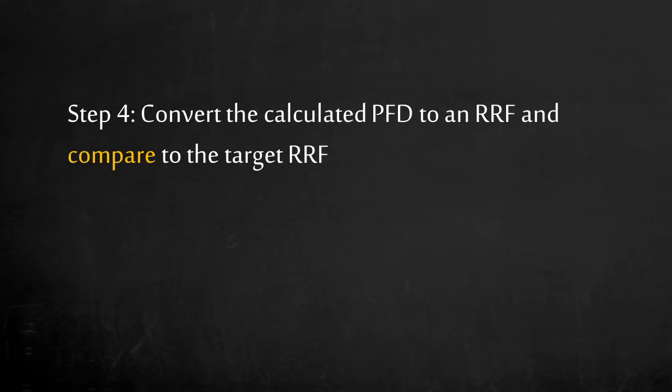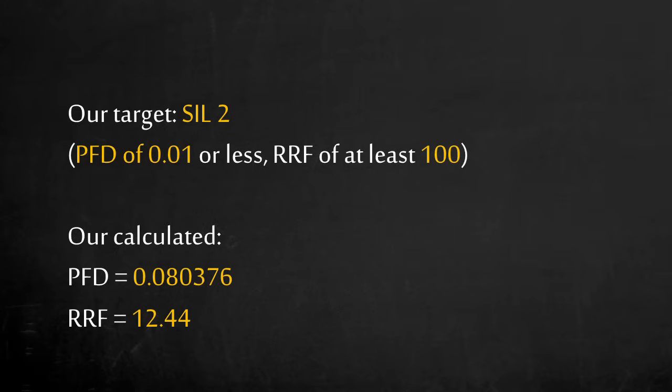Step 4. Now that we have calculated the PFD of the safety instrumented function, let's compare it to our target. The probability of failure on demand of this safety instrumented function is around 0.08, which is around an 8% chance of failure. In other words, it has a risk reduction factor of 12.44. Uh oh, the RRF isn't quite where we need it to be. We needed a risk reduction factor of at least 100.